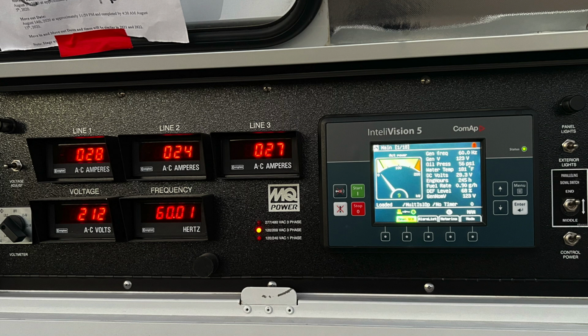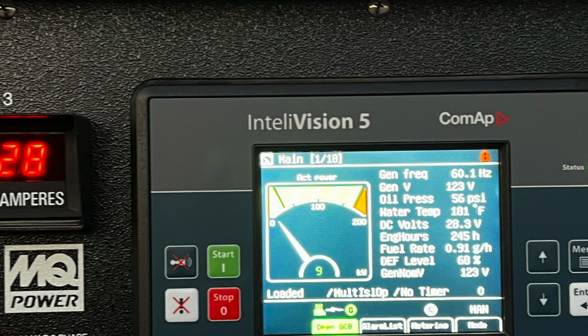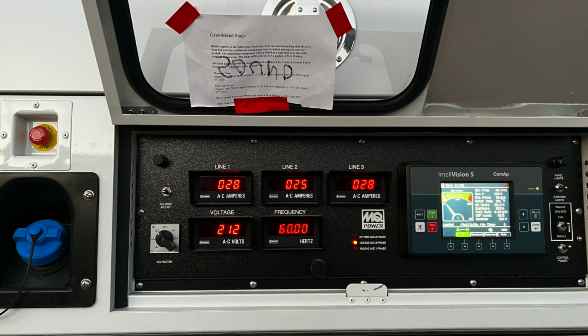One thing to note about generators is I will typically run them no more than 125 volts per phase, but I like to sit at about 123 with generators, depending on the size. Typically, if you're not carrying the generators at a huge festival, you are going to have some voltage swings. So I like to set them just a little bit hot, not too hot, so that when they get pulled down by the PA, you're still within operating range.